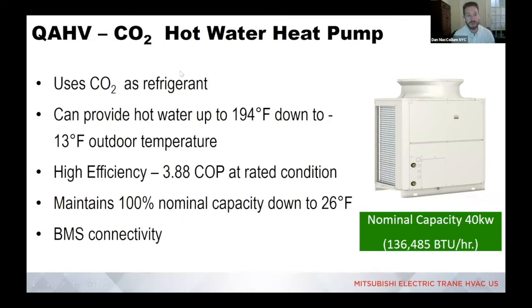It's important to note that 100% nominal capacity down to 26 degrees Fahrenheit, that's the break point or anticipated break point for where the outdoor unit will start derating. So just like a normal heat pump, there is a point where the outdoor temperature gets so low that it becomes difficult or more difficult to pull the heat out of the air. And it's about 26 degrees with this unit. It doesn't mean below 26 that it can't work. We actually have a few systems installed in Norway that we put there for testing purposes, and they've been operating pretty flawlessly down to -31 degrees. So certainly more extreme than I'd ever see in my climate here in New York.